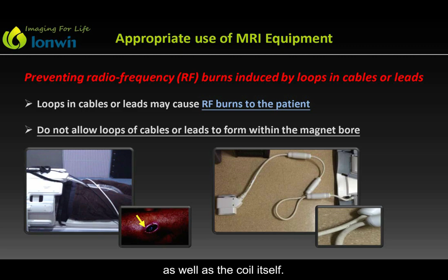Note how a loop is formed around the patient and see how the coil leads are entangled. Do not allow loops like this to form inside the MRI scanner. It's quite dangerous for the patients as well as the coil itself. Insulation pads can be used to help prevent radiofrequency burns to patients in MRI. Sponge pads separate and insulate patients from direct contact with leads, coils, or the scanner bore. These pads can be placed between the arms and legs of patients to prevent skin-to-skin contact points forming potential circuits for conducting heat energy from touching body parts.